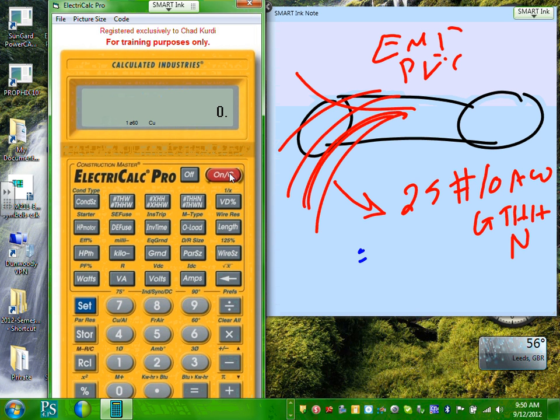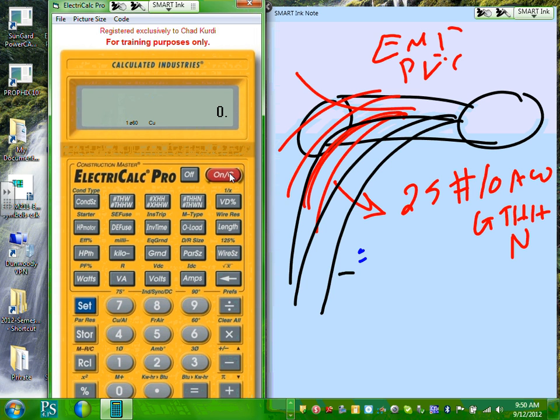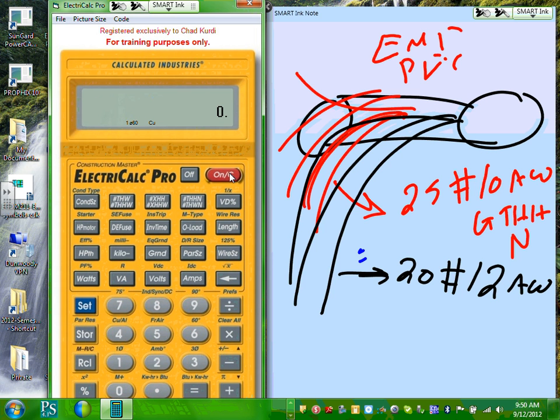Now let's complicate the situation and then let you go. Let's add another set of conductors that are different. I have another 20 conductors, number 12 AWG THHN. Now we have two sets of conductors, different conductors. I have 25 of number 10 and 20 of number 12.